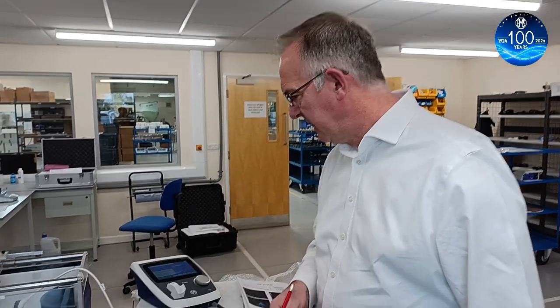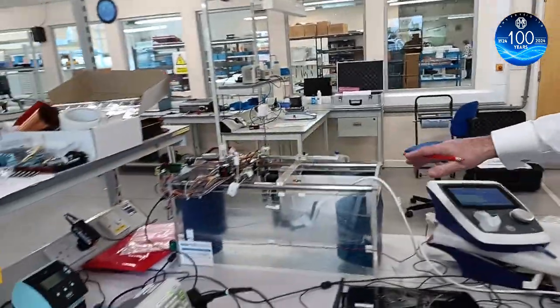Two of the other important features to measure in ultrasound are the ERA and BNR. The ERA is the effective radiating area. The BNR is the beam non-uniformity ratio. Both of these values are determined and set in the International Standard 60601-2-5 for therapeutic ultrasound devices. What we use to determine that is an ultrasound scanning tank.